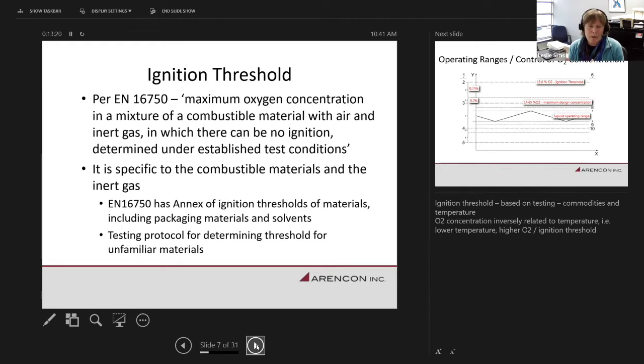Within there, they define the ignition threshold as the maximum oxygen concentration in a mixture of air, between the combustible material in the air and the inert gas, where there's no ignition, under established test conditions. And the test conditions are, I would say, kind of like a small scale test. The test conditions are basically a 10 by 10 by 10 meter container or space, and the material is placed in that space.